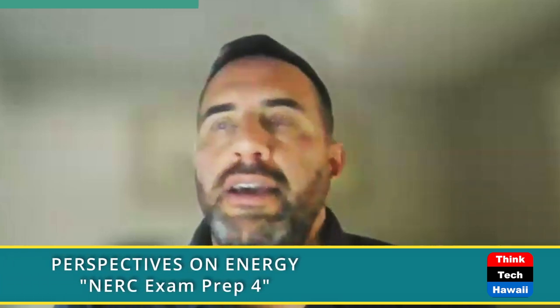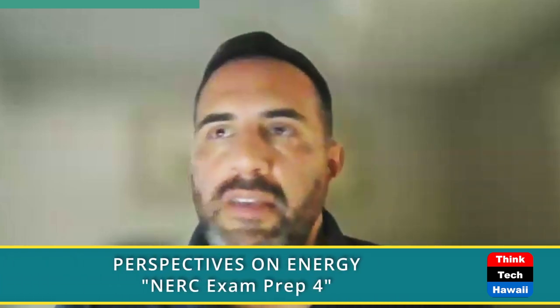So most generators have what they call a capability curve. They call it the D curve. D is in delta, because it looks like a D. So this capability curve really is, once you're at the highest real power output, you don't have any more room to either absorb or put out vars. So if you decrease, for example, the real power just by 3%, 4%, 5%, you're giving yourself a really significant 10-15% ability to use that to send reactive resources out into the system.